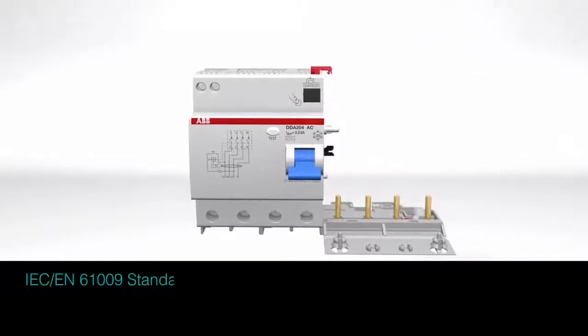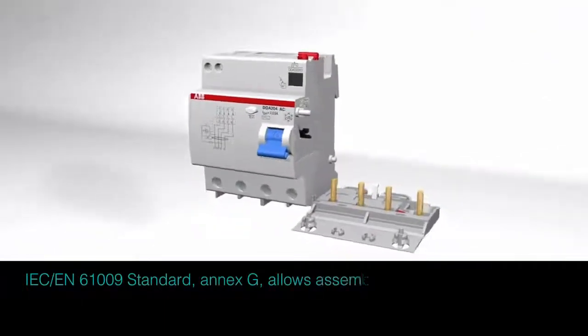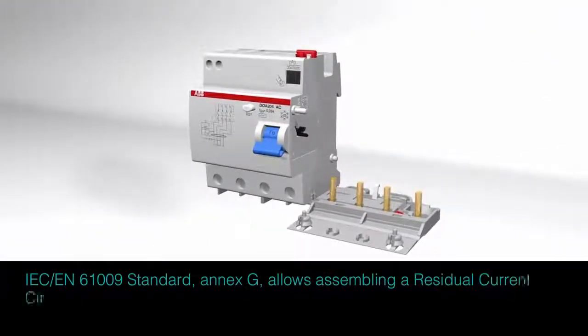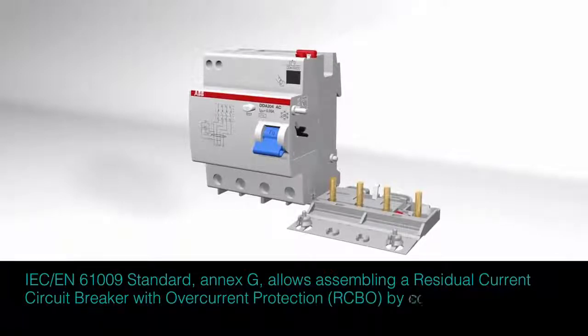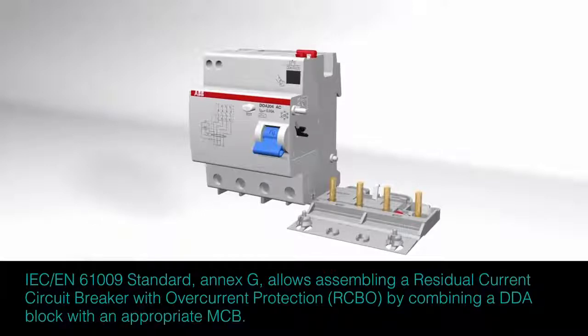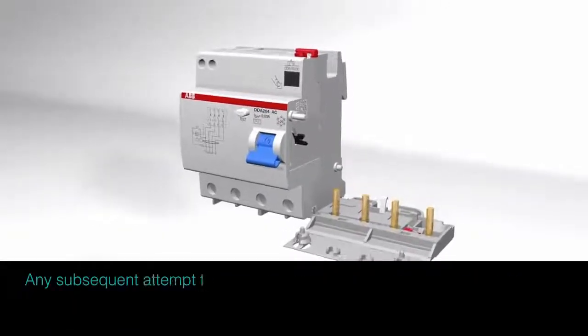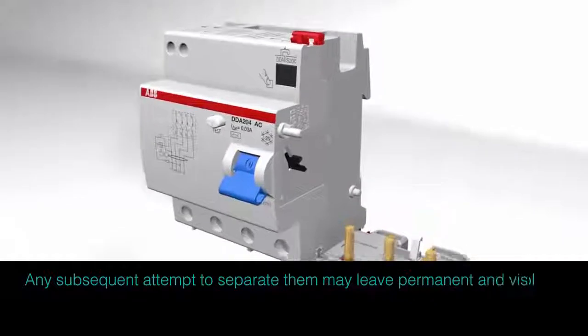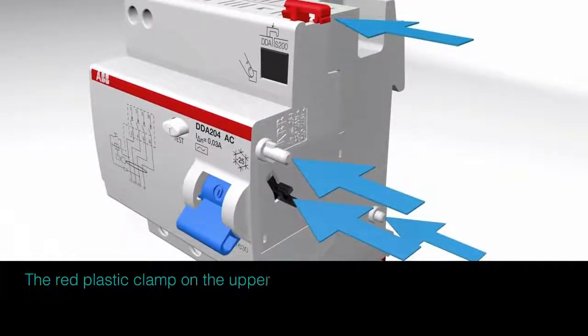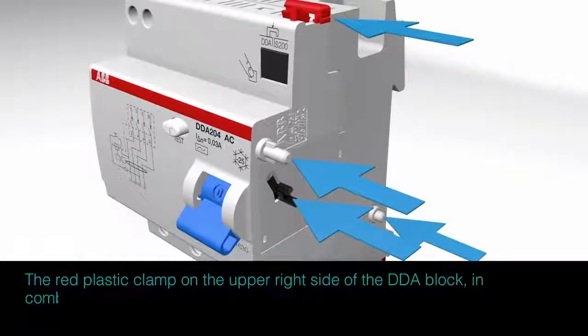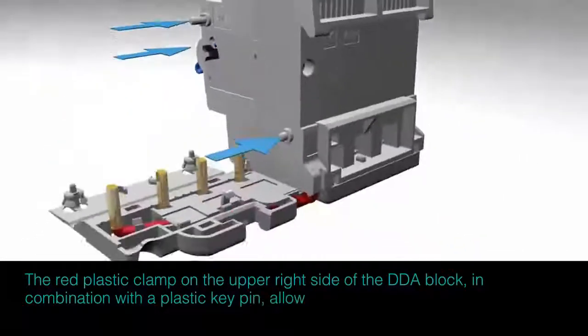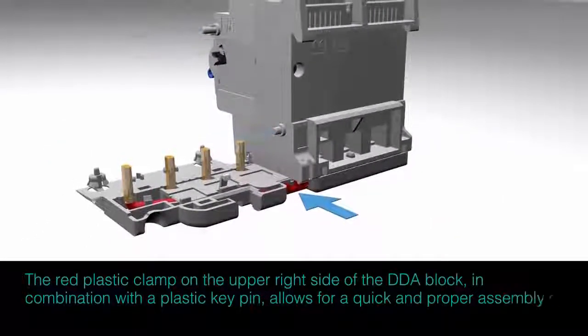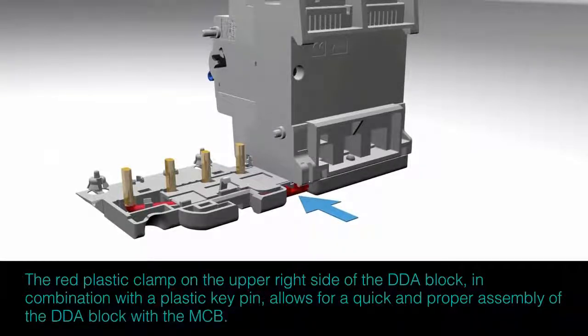IEC EN 61009 standard Annex G allows assembling a residual current circuit breaker with overcurrent protection, RCBO, by combining a DDA block with an appropriate MCB. Any subsequent attempt to separate them may leave permanent and visible damage. The red plastic clamp on the upper right side of the DDA block, in combination with a plastic key pin, allows for a quick and proper assembly of the DDA block with the MCB.